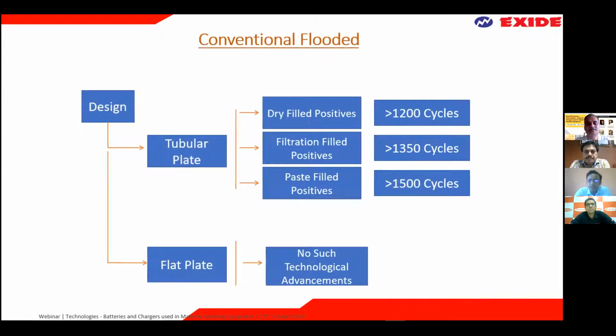Now, for the conventional vented lead acid battery, that is the flooded type, there are basically two designs: tubular and flat. Flat plate didn't have any technological advancements, but tubular has basically three types of positives: one is a dry filled positive, one is a filtration or slurry filled positive, and the third is a paste or extruded filled positive. The cycle life of the batteries depends basically on the manufacturing process of these plates.